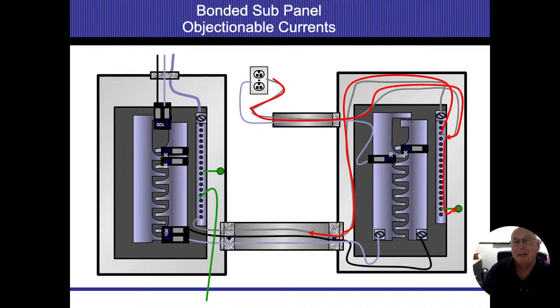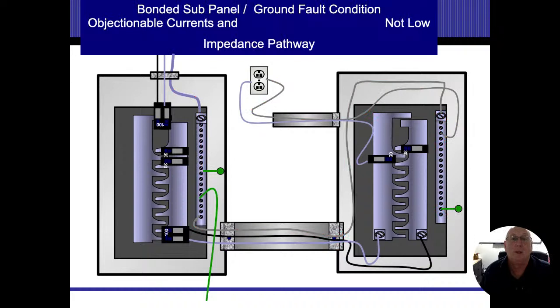No doubt on that. But because I'm bonded there as well, I'm putting a connection to my electrical panel. Electricity is also going to be flowing on my electrical panel. So now, as long as electricity is flowing, depending on how much amperage is being used, I'm going to have amperage on my conduit system between the panel and the sub panel. And if somebody touches that and something else that's zero, then they can start creating an ulterior flow, and they can actually get themselves shocked or electrocuted. So having that secondary bond, I'm sorry, it's not good. Plain and simple.